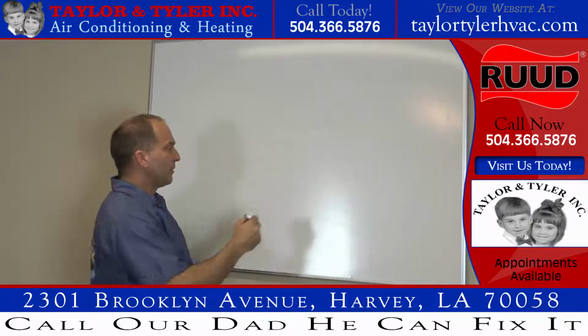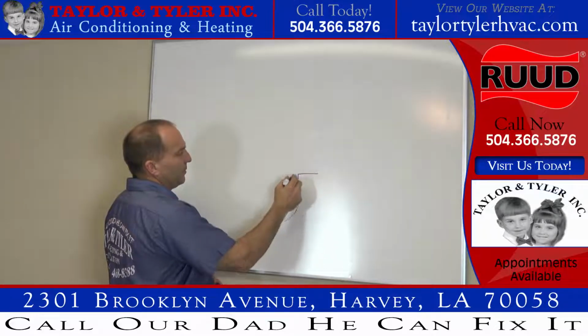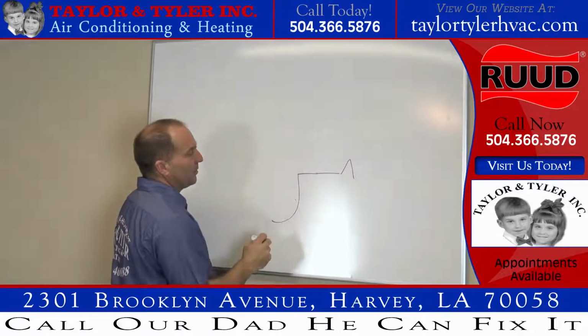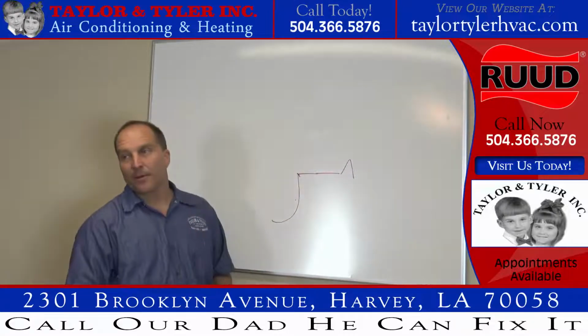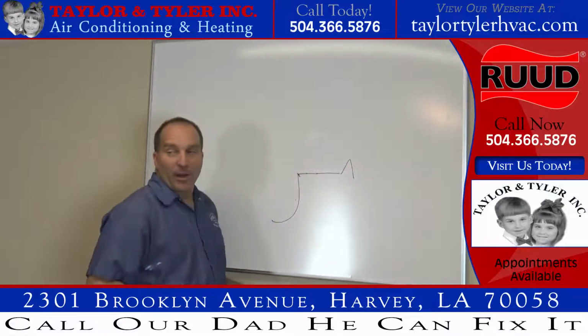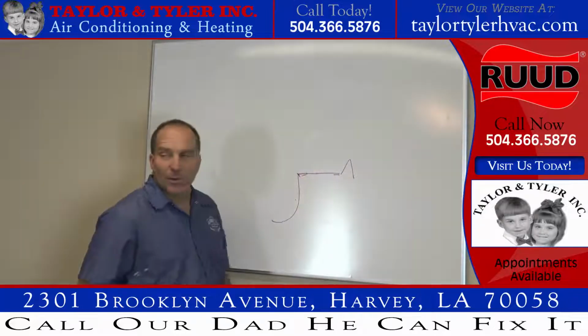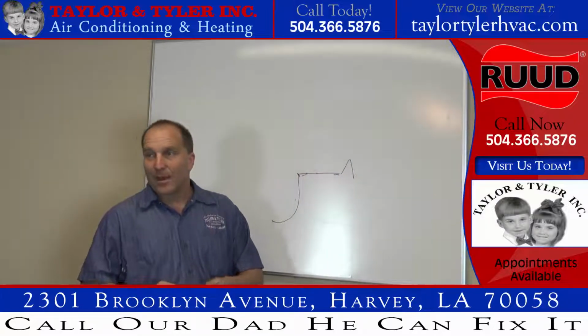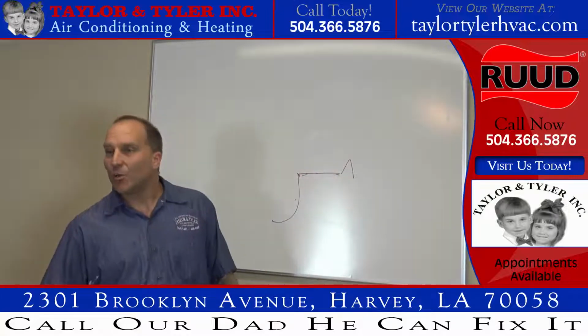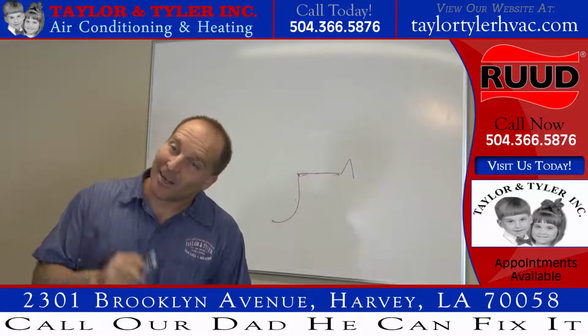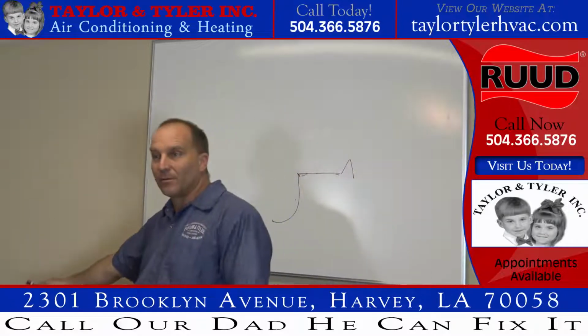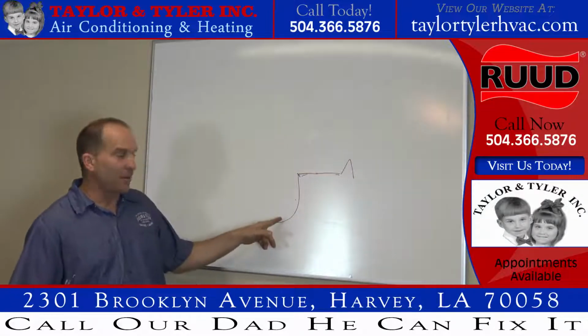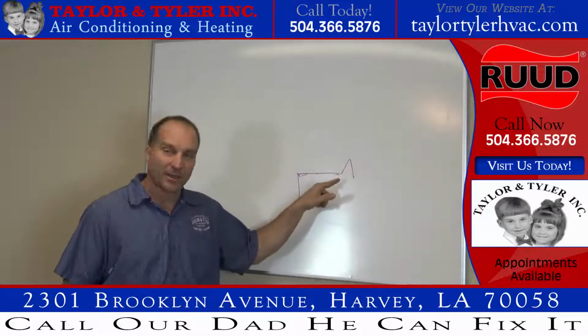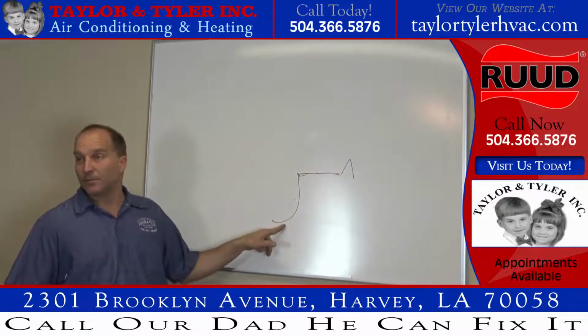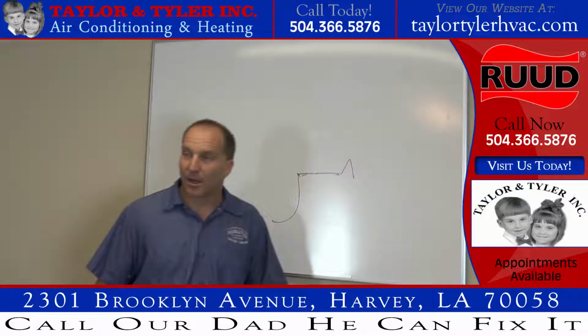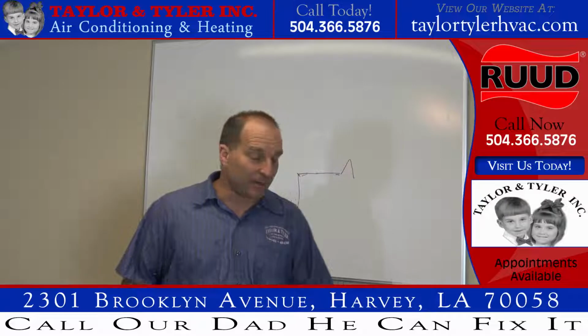Because your restriction was coming up here and then went all the way over to your evaporator coil, right? So if your restriction, your kink was right there, it's going to drop in pressure right here, and it's going to start making this liquid line cold. So you may go to that evaporator coil and see your liquid line sweating. If you see your liquid line sweating, there is a restriction before, okay? So you have to trace it back. If you come outside and it's not sweating here, you go inside, it's sweating in here. Somewhere between here and here, you got a restriction. Okay?